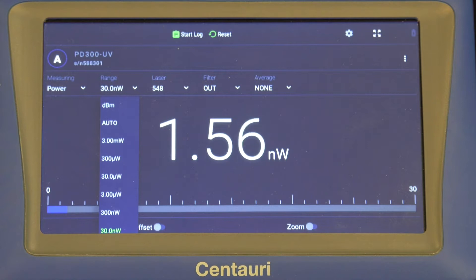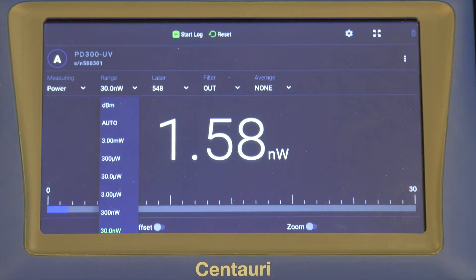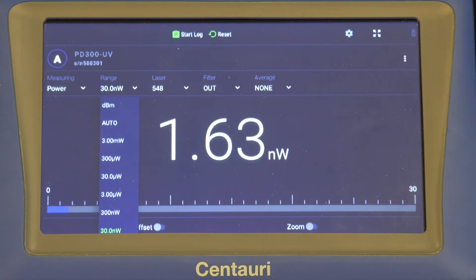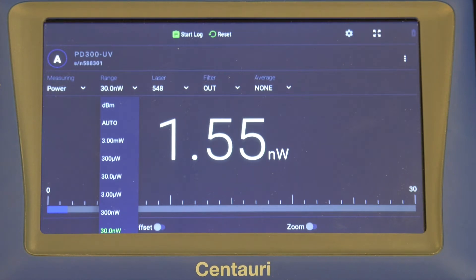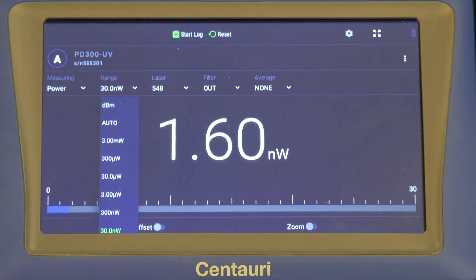The user can select the 30 nanowatt scale, the 300 nanowatt scale, and so on. They're quite typically configured to be one order of magnitude apart, and the user selects the appropriate one for the expected measurement.